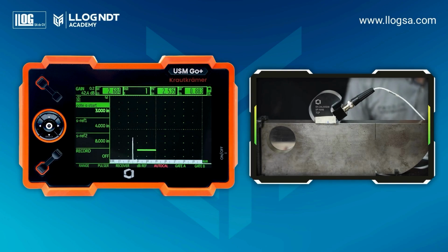Refraction angle verification. To verify the refraction angle, use the graduated scales on the side of the IIW block. Go to the Auto Calibration menu, then select Auto Angle. Based on the block and angle to be used, select the corresponding block and graduation on the instrument. In this example, since we are using a 70-degree angle, we select the IIW block for the 60 to 75-degree range. In the block function, the instrument displays two values: 2 inches, which is the borehole diameter, and 1.2 inches, which is the depth from surface to the borehole center.